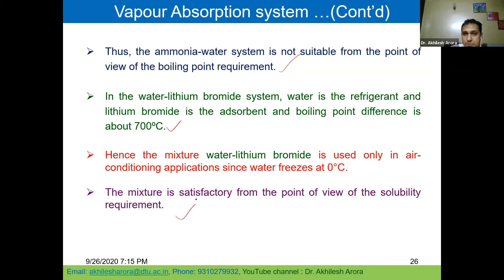Now, since lithium bromide is a salt, it exerts no vapor pressure in the generator section. So the vapor leaving the generator is a pure refrigerant. The mixture therefore satisfies the boiling point requirement also. However, this is a very important point for the water lithium bromide system. It is corrosive and the plant works under high vacuum. In the ammonia water system, it is positive pressure everywhere, but the water lithium bromide system works under negative pressure, both in the condenser as well as in the evaporator. So a purge unit is required in the case of the water lithium bromide system.